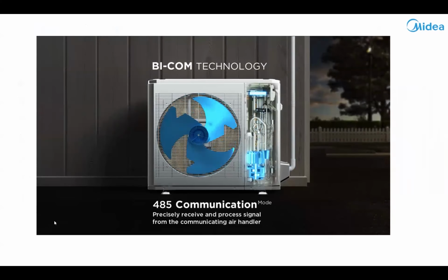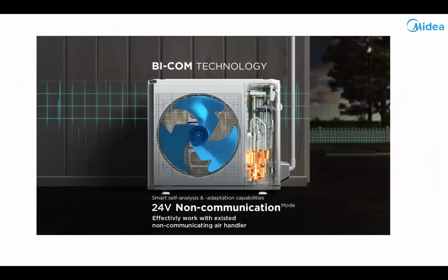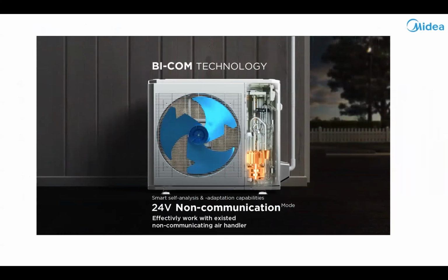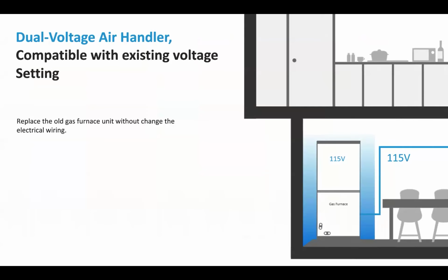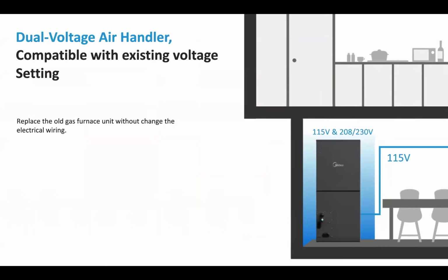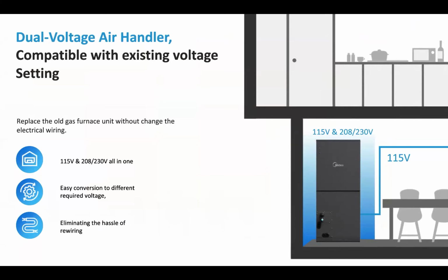All right, 485 communication. That's the method we prefer. Or you can use a 24 volt thermostat with S1, S2 communication between the indoor and the outdoor. Reason we made this dual voltage is so we can take out a gas furnace and put this air handler in its place without having to make any major changes in the wiring. It's an easy conversion for different required voltage. Again, it's auto detecting. So if you wire it for 115 or 208/230, it will take off and run. There's nothing to change.